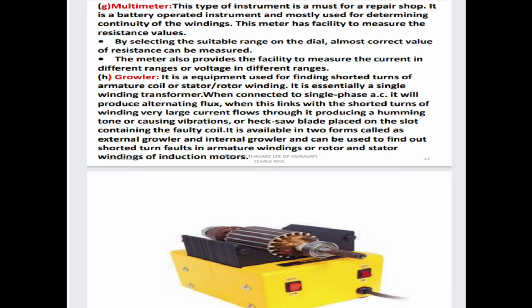And then the growler. This is the diagram of a growler. It is equipment used for finding shorted turns of armature coil or stator or rotor winding. It is essentially a single winding transformer. When connected to single phase AC, it will produce alternating flux. When this links with the shorted turns of a winding, a very large current flows through it, producing a humming sound or causing vibrations of a hacksaw blade placed on the slot containing the faulty coil.